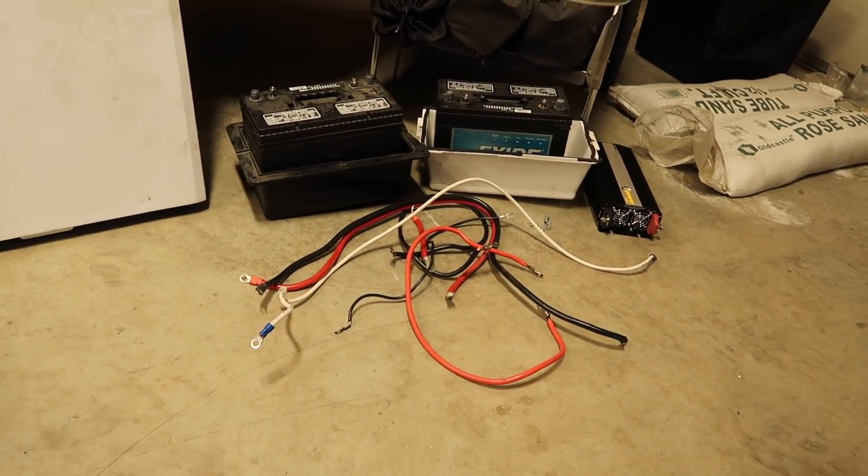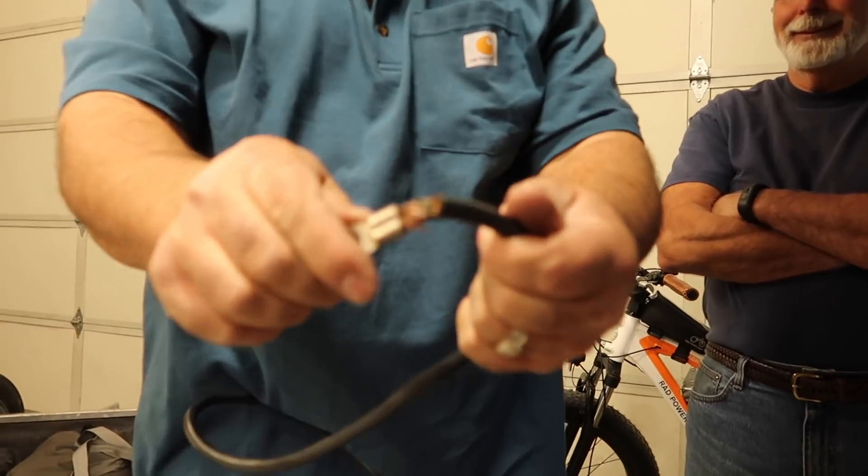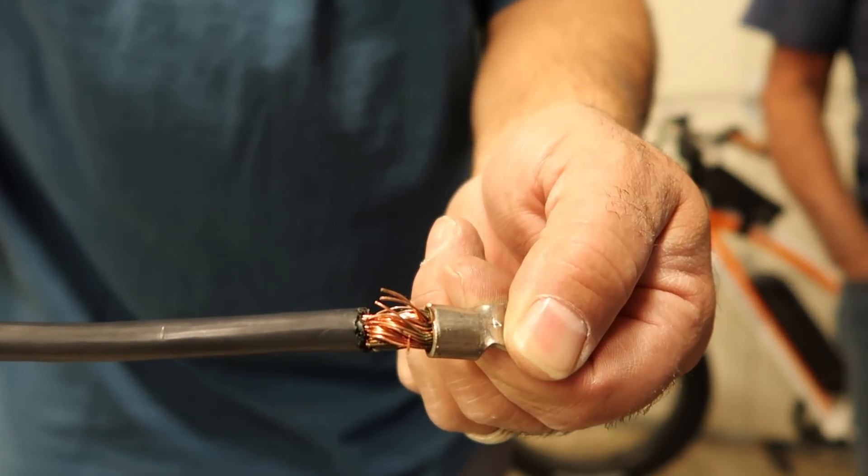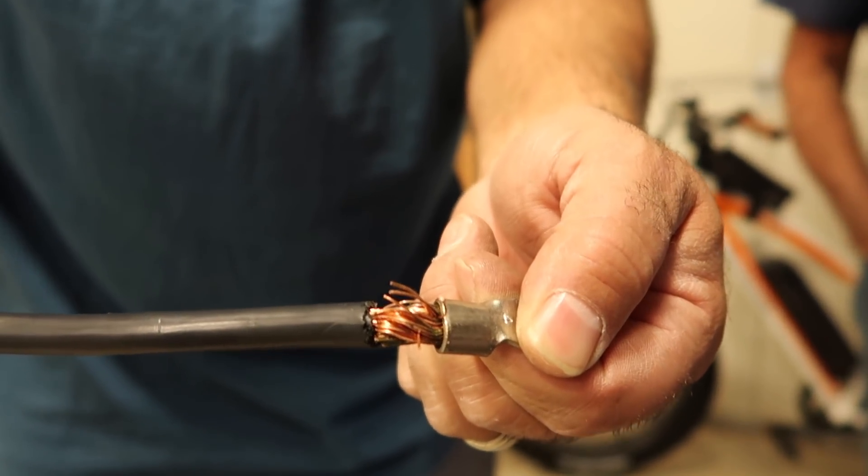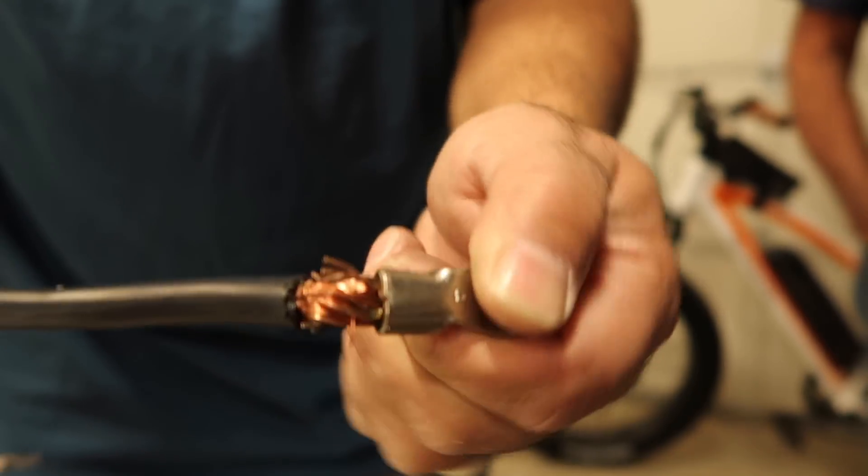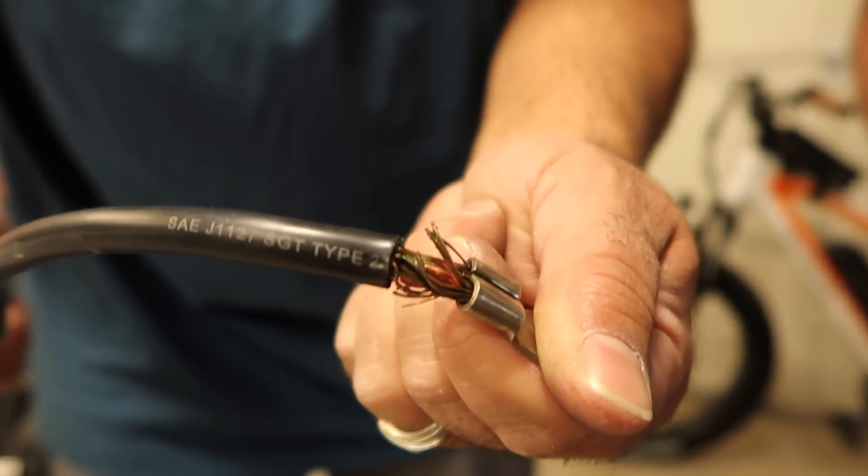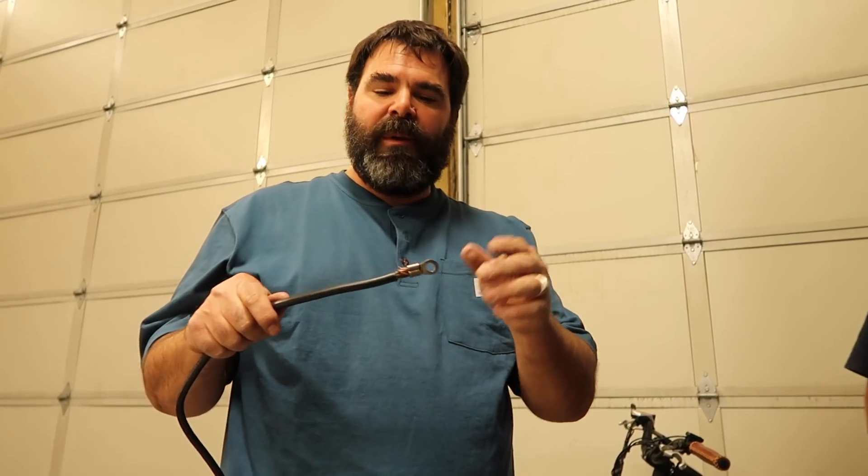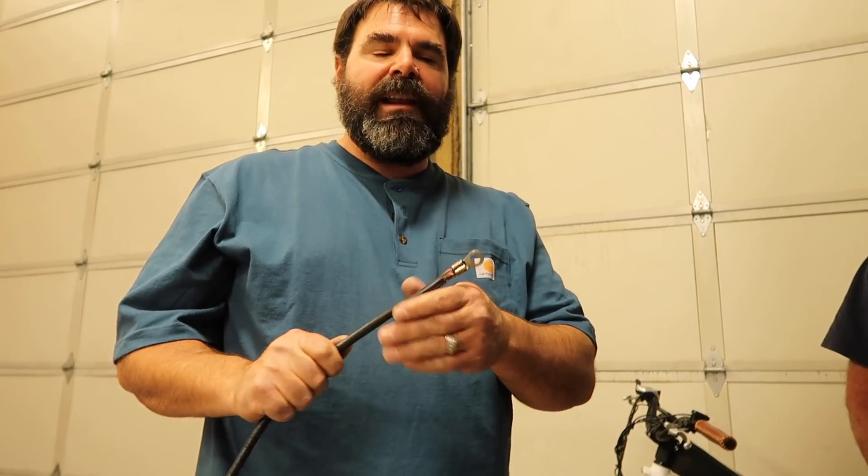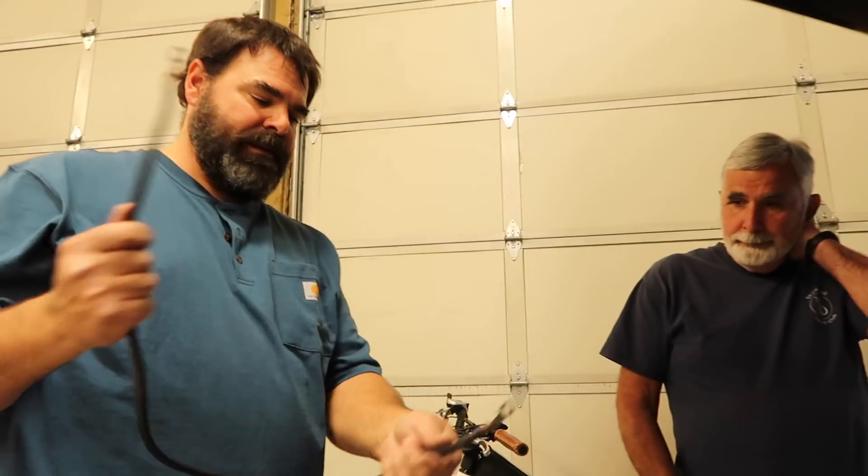Oh, it's nice to be able to reuse. Shocking. Look at that. Look at that, isn't that nice? So this is a deal I believe either a dealer or it could be possibly a manufactured install item. Look at how many wires they missed out of that crimp, and it's all fraying apart. So once a year you need to get in there and check your cable and make sure stuff hasn't frayed loose. Make sure everything's nice and tight on your connections. All of your battery connections and all your cable connections need to be really nice and tight. So make sure you get that stuff done. That way you limit, you're lessening the resistance, less chance of any kind of heat issues and fires. That's important.